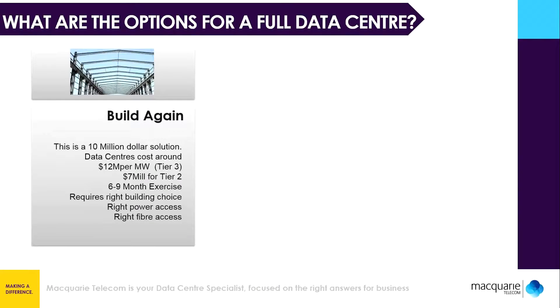With full data centers, what options do we have? Firstly, you can build a new data center — this is really the 10 million dollar sledgehammer solution. I've been involved in building about four to five data centers, and a premium data center costs about 12 million dollars per megawatt; a lower quality one is still about five to seven million. This can take up to a year to deploy, and you can only go on that journey once you've actually found the site. In Canberra, we looked at about eight different locations, did full costings on three, and the whole process took about eight months before we found the land we wanted.